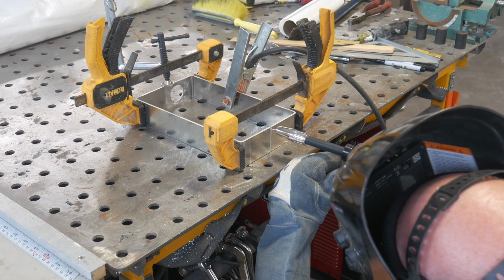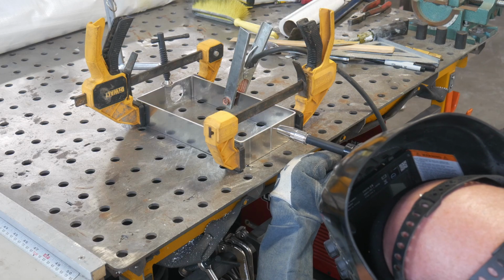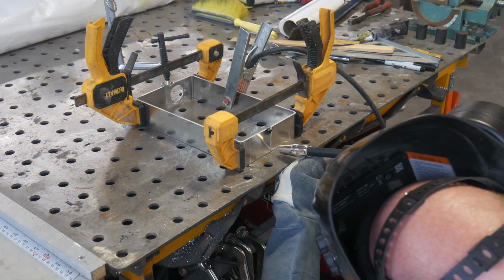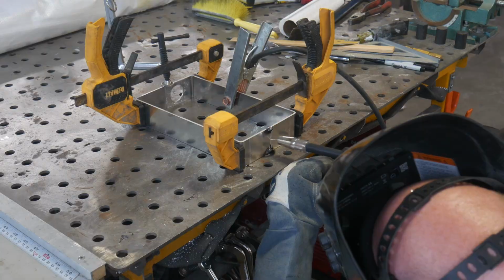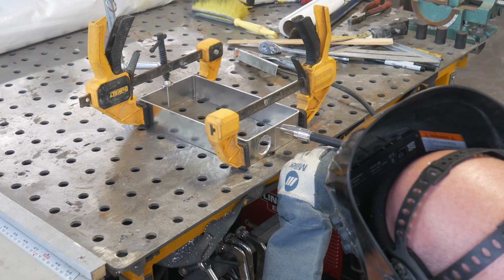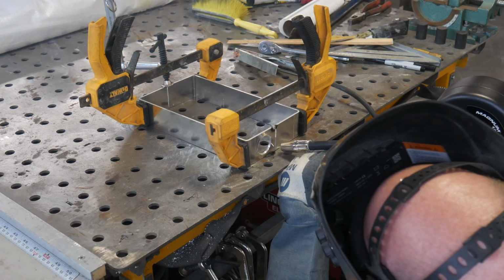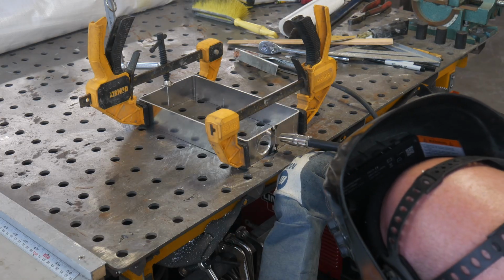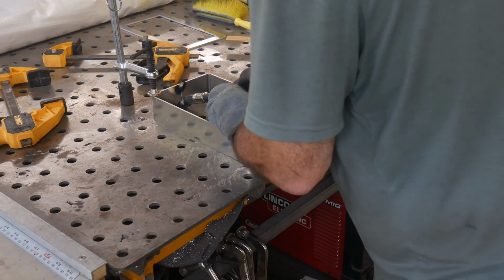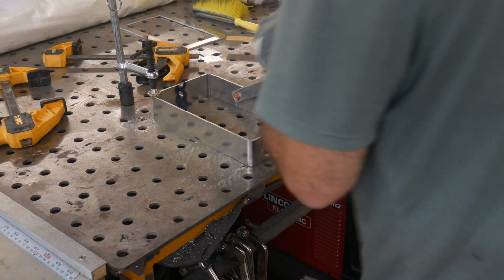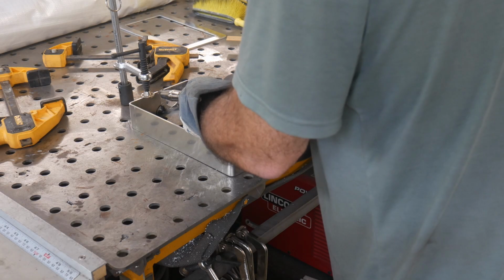The top does not have end conditions, as the lower box ends go the full height, but we do need to install a little doghouse, which provides room for and access to the high voltage connection on this end. As with the bottom, we have drilled a hole for the cable gland needed for the high voltage line. We have also drilled a hole in one of the access covers for a breather valve that will allow the pressure in the sealed box to stay constant as the batteries get warmer or cooler.